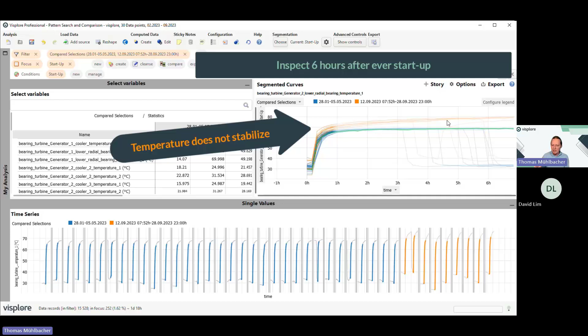then you see that actually the temperature does not stabilize during the incident, but it's really increasing and increasing, where usually it stabilizes at 70 degrees after 2 hours. So it's rising until the turbine is switched off again. That's a problem, proven on the historic data. But why do we have this problem?